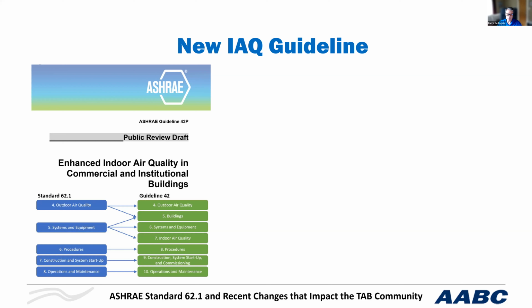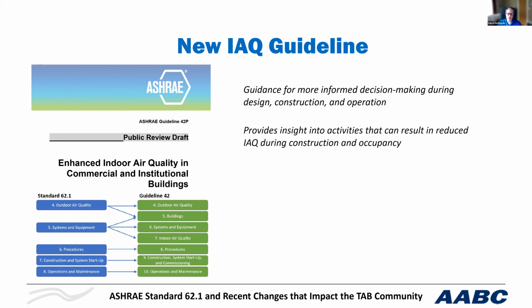And again, we talk about ASHRAE 62. ASHRAE 62 is the minimum standard. It's not the speed limit, though a lot of people treat it as a speed limit. And if we start with it being the speed limit, and then we start having problems with our engine and we can't achieve the speed limit, then we're going to be underventilating. So this is a way to provide more ventilation and enhanced indoor air quality. It goes beyond the standard and the user manual to try to achieve that.